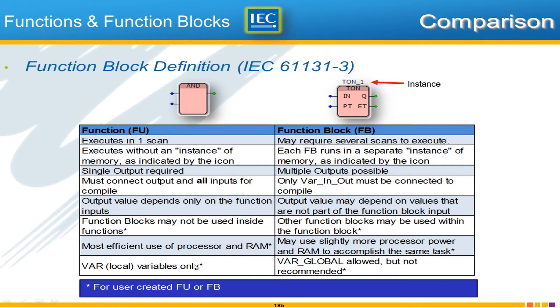Related to variables: when you create your own function, you will not be allowed to use global variables. You can use global variables inside function blocks, but it's not a great idea because those global variables must exist in any future project where you'd like to use your custom function block. We recommend that if you have data to add to the function block, don't include it as a hidden global variable input — instead, make it an explicit input. In another video we'll show how to make a custom function and a custom function block.